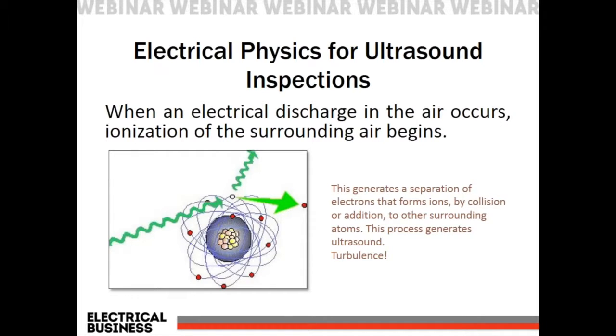So, electrical physics for ultrasound inspections. When an electrical discharge in the air occurs, ionization of the surrounding air begins, which is where we're getting the turbulence from. This generates a separation of electrons that forms ions by collision or addition to the surrounding atoms. This process generates ultrasound, and again, as I mentioned, it creates turbulent flow, which allows us to hear these sounds.